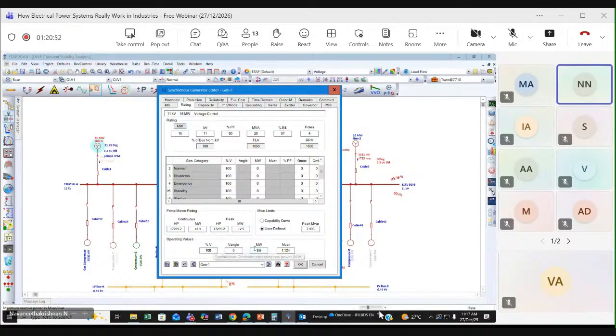Because gas turbine generators are derated, somebody can ask: you said 16 megawatt here, but you are only operating at say 12 megawatt. These gas turbine generators operate at a rating that depends on your operating atmospheric temperature, the inlet air of the turbine, because turbine ratings are given as ISO rating. Everybody knows ISO rating: it is designed for 15 degrees centigrade. So they will derate accordingly. When the temperature goes up in summer, you will get only 10 megawatt sometimes, and when the temperature drops in winter, it goes to 16 megawatt. That is why we have taken the worst case scenario, the highest ambient temperature.